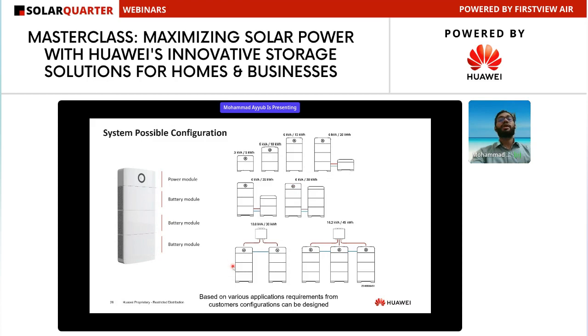But we can also connect multiple power modules in parallel. In this case, we are connecting two iSitePower-Ms in parallel, giving a power capacity of 10.8 kVA and energy capacity of 30 kilowatt hour. Similarly, we can have a maximum of three in parallel, where the power capacity is 16.2 kVA and the energy capacity is 45 kilowatt hour. So we can play with the power capacity, and we can also play with the energy capacity.